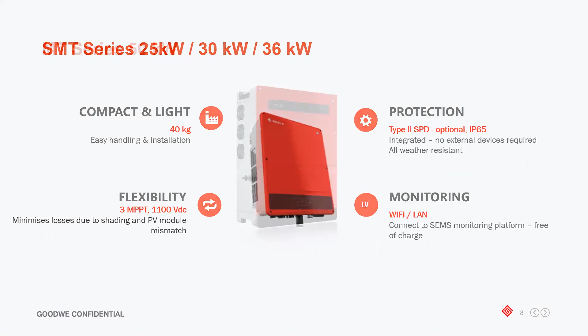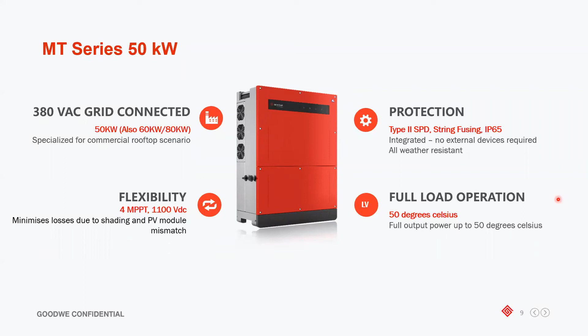So the MT series, available in 50, 60, and 80 kilowatts, has been our most popular inverter to date for commercial PV plants from anywhere from 50 kilowatts to 20 megawatts. Its low voltage output of 380 volts is specifically designed for commercial and industrial low voltage applications. So this means that no external step up or step down transformer is required to connect into the low voltage grid. It also comes equipped with 4 MPPTs and type 2 surge protection as standard, and includes string fusing. By virtue of its fans, the inverter has a full load operation of up to 50 degrees, which is significantly higher than inverters that are designed with no active cooling.